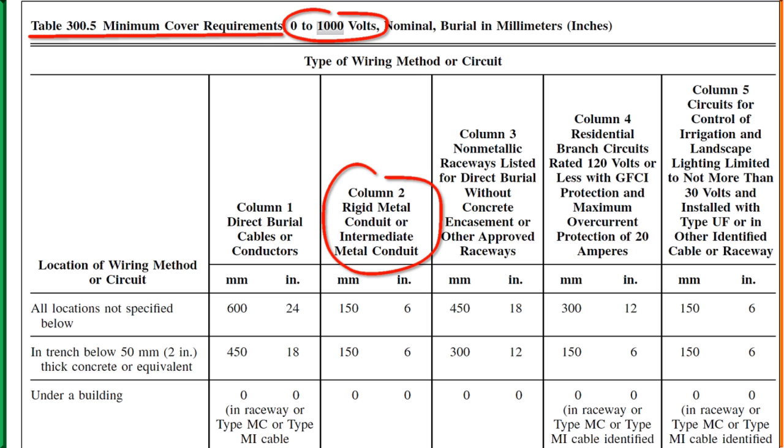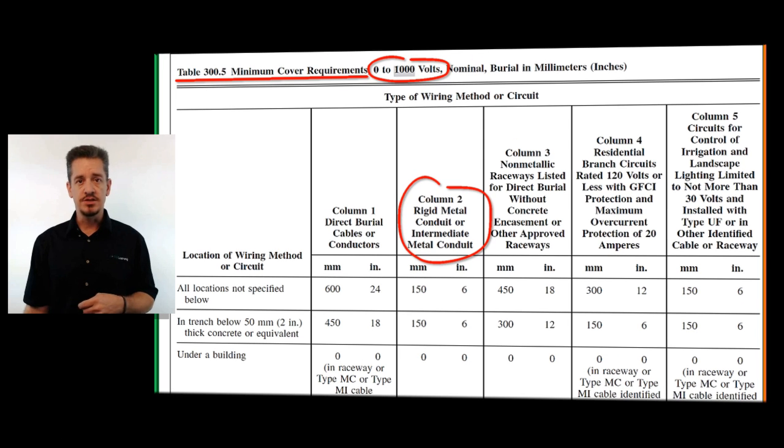Look at column two. Rigid metal conduit or intermediate metal conduit. Does it say anywhere in column two, rigid metal conduit or intermediate metal conduit with wires in it? No, it does not. Most of the dimensions in that column are going to say six inches. There's one in there that says four inches.